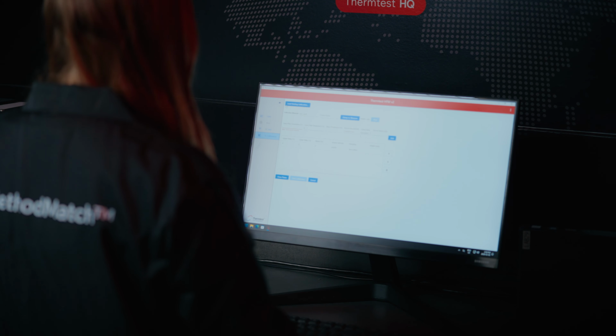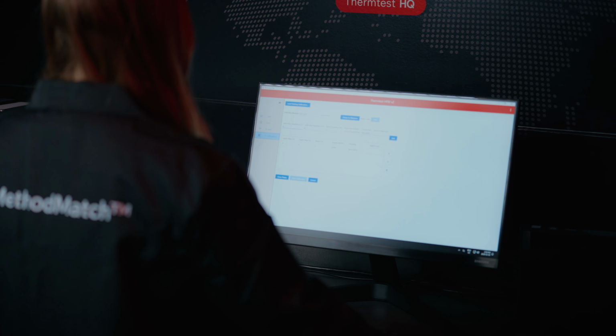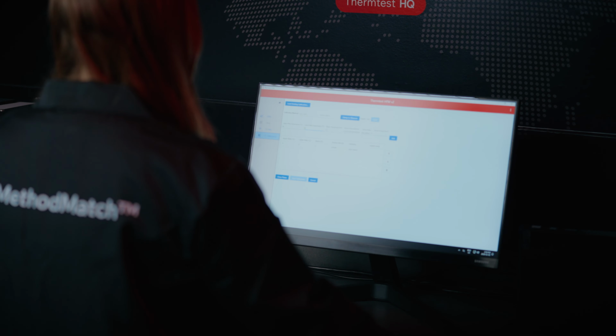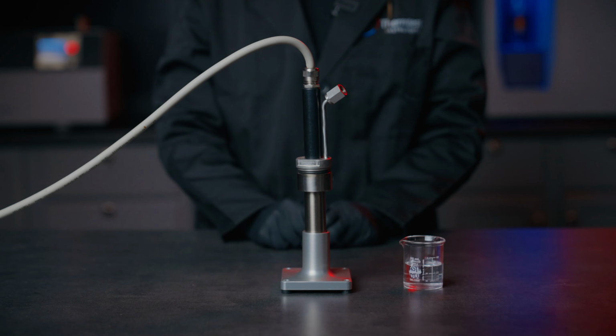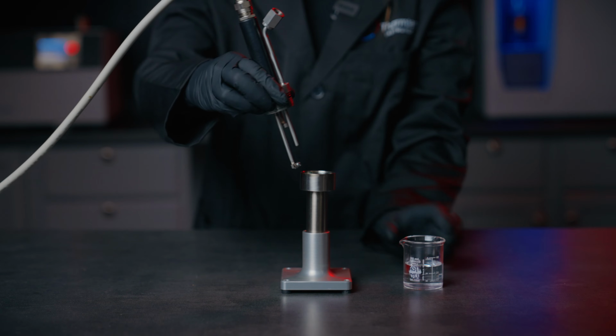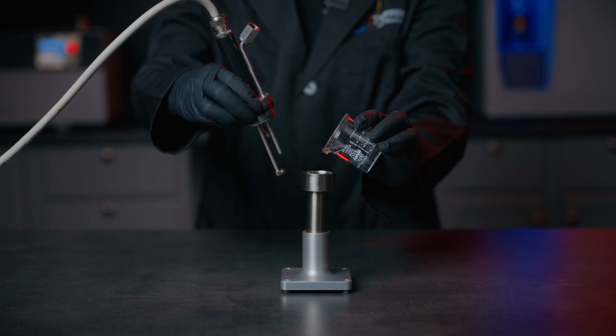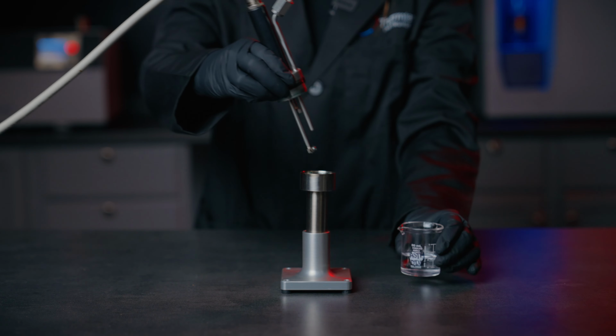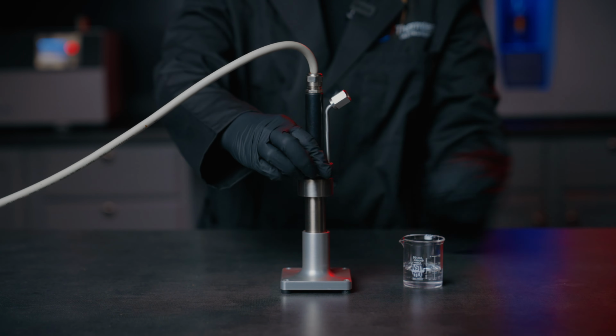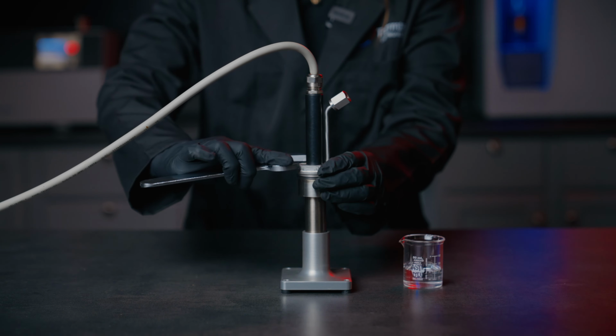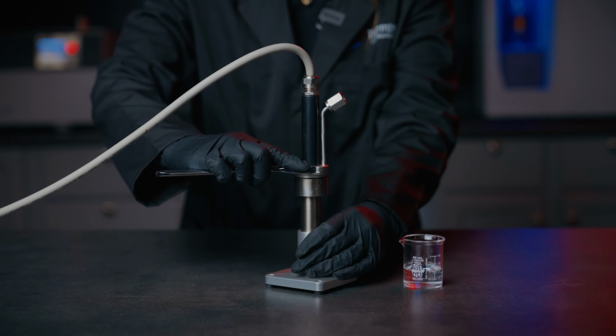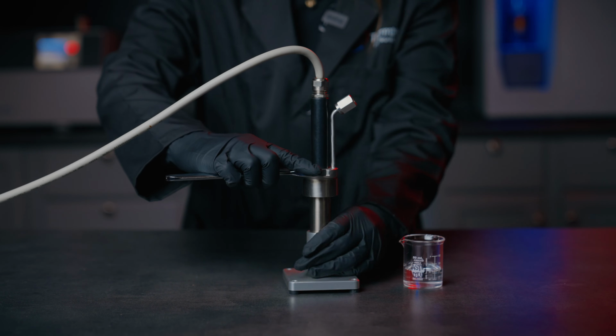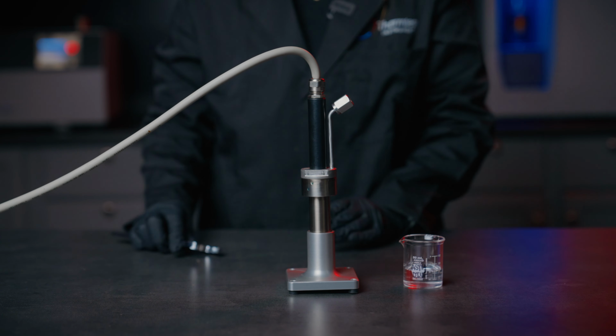Calibration directly impacts both accuracy and repeatability. A properly calibrated instrument produces results that fall within a specification and can be confidently compared across samples, tests, and even laboratories. Verification, on the other hand, is the process of testing a certified reference material against the calibration to confirm the instrument is still performing as expected. Verification should be performed regularly, especially after environmental changes, heavy usage, or software updates. If a verification test fails, that's a clear signal that a recalibration may be needed.